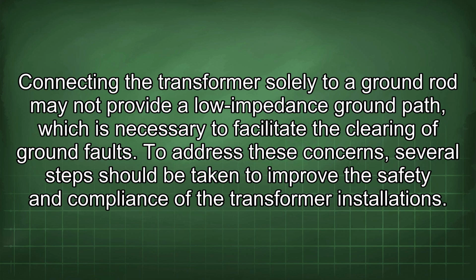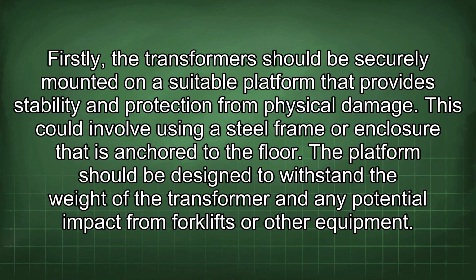To address these concerns, several steps should be taken to improve the safety and compliance of the transformer installations. Firstly, the transformer should be securely mounted on a suitable platform that provides stability and protection from physical damage. This could involve using a steel frame or enclosure that is anchored to the floor.